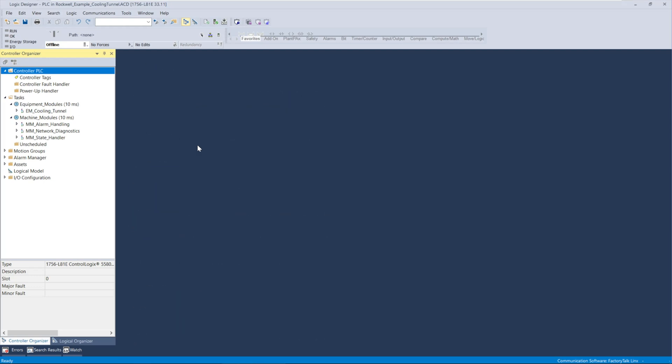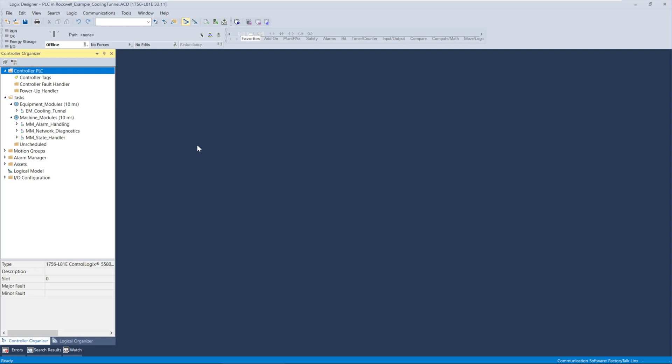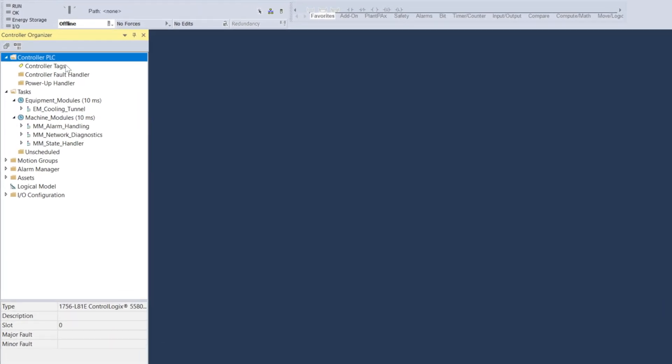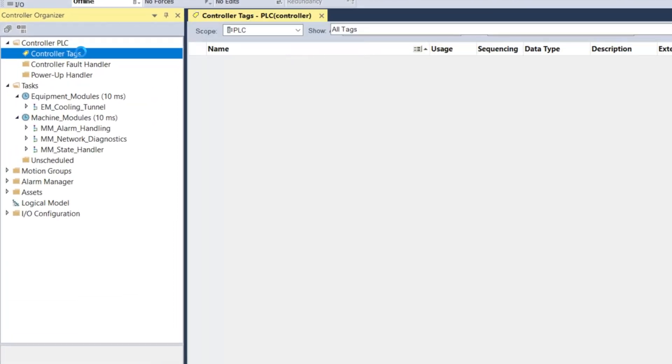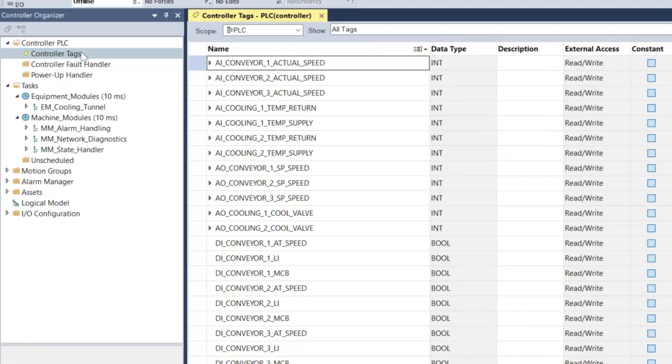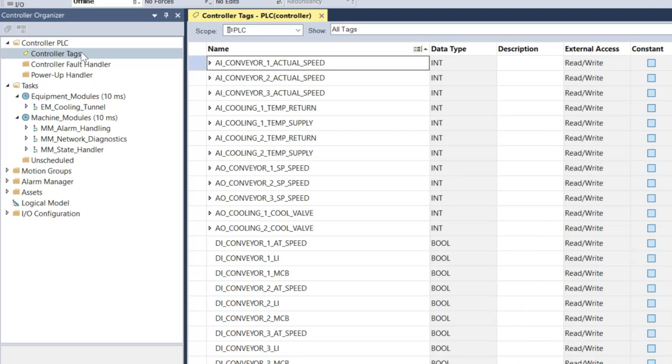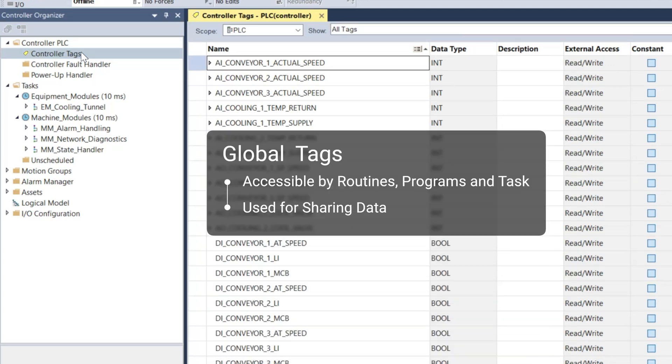Global tags, or controller tags as they're also called, are created in the controller tags section of the studio 5000 environment. Once created they can be accessed by any routine, program, or task in the project without any additional steps.